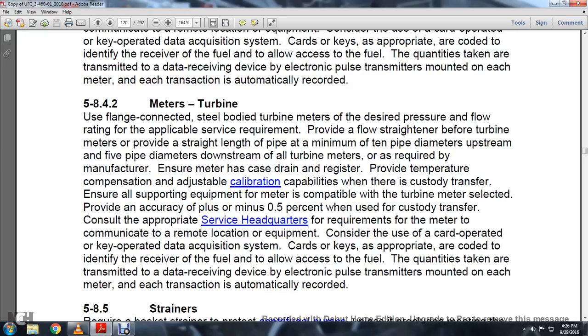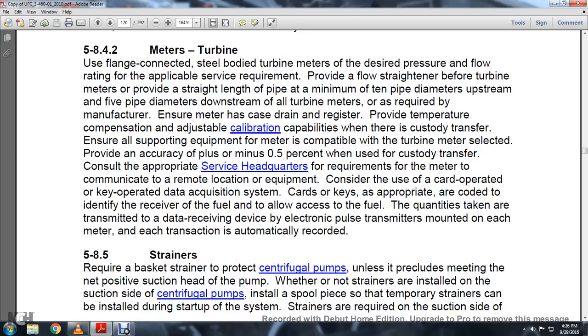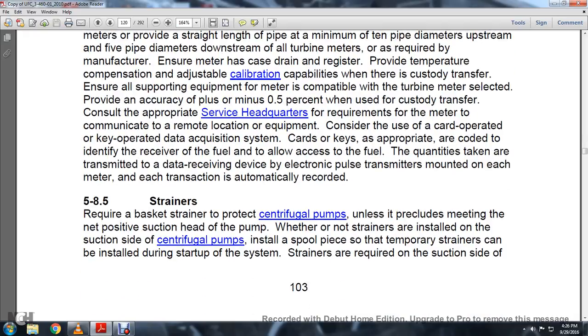Consider the use of card operated or key operated data acquisition. Cards and keys are appropriate with the code identifying the receiver of the fuel to allow access to the fuel. The quantities taken are sent to the data receiving device, with an electronic pulse transmitter mounted on each of the meters, and each transaction is automatically recorded.